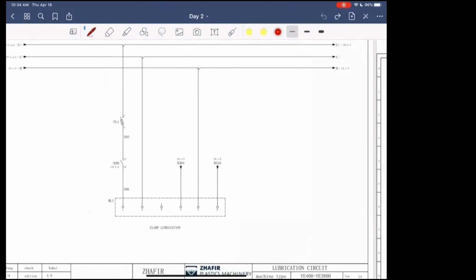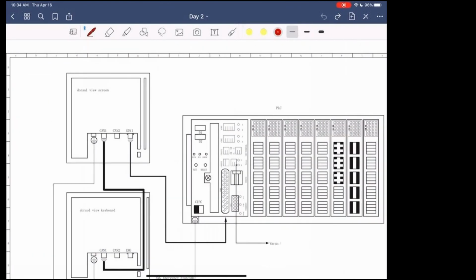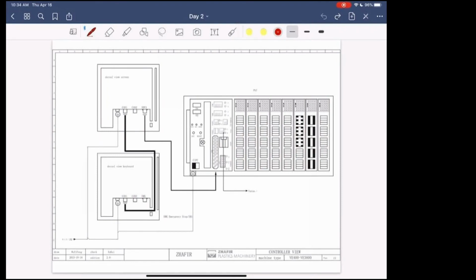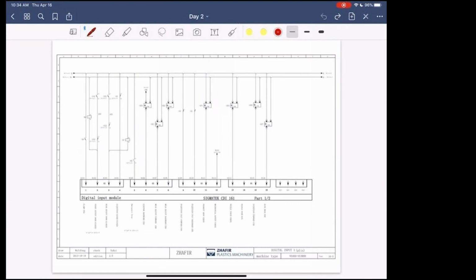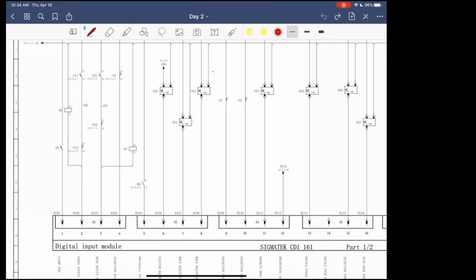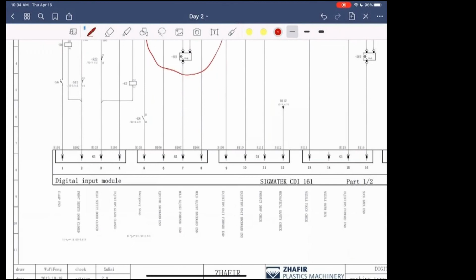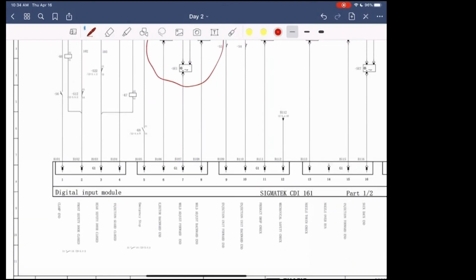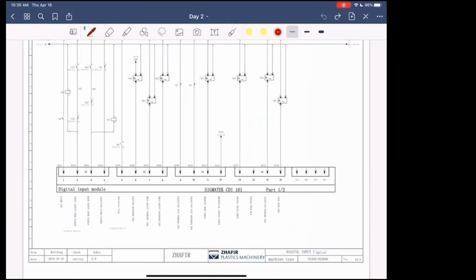This is the lube pump circuit for the clamp. And again, this is just a controller view of the hookup for the controller. This is the digital input signals. Again, we're using PNP prox switches, and the prox switches control the mold adjust forward, mold adjust back, inject unit forward, inject unit back, product drop check, nozzle touch check, injection forward end, suck back end, your mold adjust forward and back, and your ejector backward end.